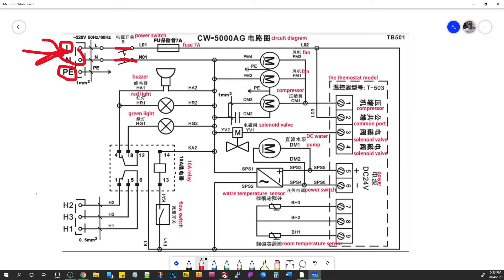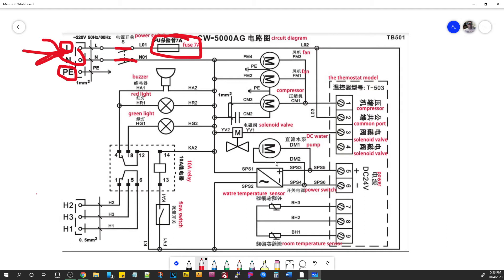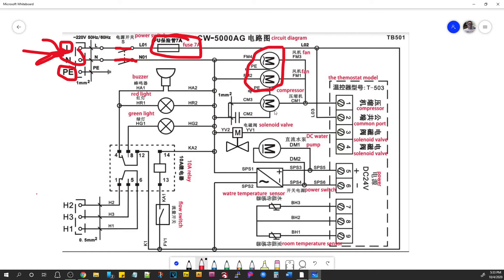This switch gets clicked on and it goes through a fuse. That is probably the number one thing you should always look for. And then after that, it powers everything that has to do with the chiller with the exception of a few 24 volt things. So these are your case fans. Those are all wired to go along with the compressor. So if the compressor is running, the case fans are running. All of those are AC. The compressor is AC.